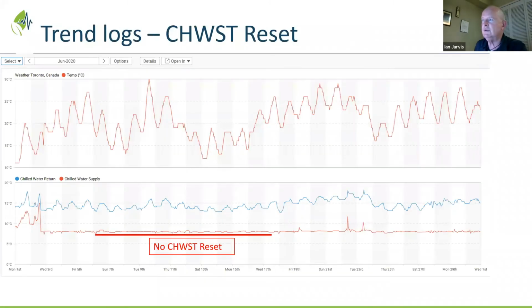But these controls issues take us to, and I'll ask Amandeep to share a few thoughts. One of the disappointments we had was that very few hospitals have trend logs set up or archived on key things like which chillers are running, which cooling towers are running, what's the chilled water supply temperature. So Rob Simpson, who was on just a second ago at Ontario Shores, was kind enough to share. And if you remember, he's already at his cooling electric target. So he's a very efficient plant. But the trend logs here, this information is showing there's still more to be done.